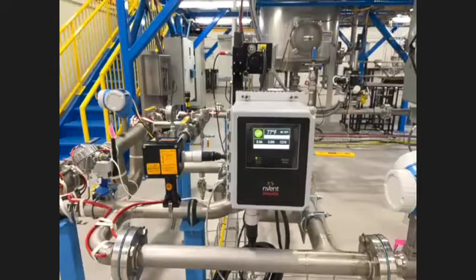So what I'll just show you here is this is one of our fundamental or basic heat trace controllers. In summary, it's a fancy thermostat with a touch screen. It provides a lot of things that are required. For example, 30 milliamp ground fault protection is the most prominent feature of this controller. All heat trace needs to be 30 milliamp ground fault protected. That's typically achieved through a ground fault breaker with a 30 milliamp rating or a controller. We prefer controllers for various reasons, but in summary, it's a thermostat providing monitoring as well as control and providing the 30 milliamp ground fault protection.